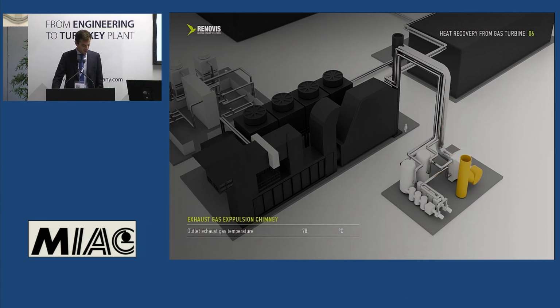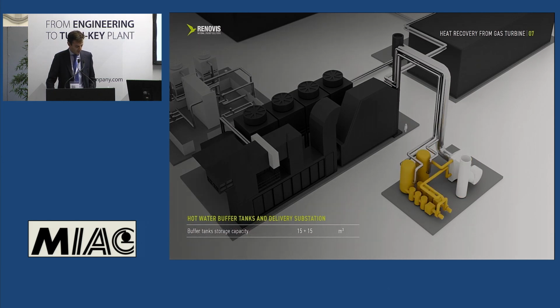Recovering thermal energy from the fumes obviously means that they undergo a cooling down to about 78 Celsius degrees, and they are then expelled into the atmosphere by means of a new chimney, specifically built for this purpose. The hot water generated through the heat recovery is stored in two inertial tanks of 15 cubic meters each. Their function is to temporarily separate the production of hot water by means of thermal recovery from its use, optimizing the efficiency of the overall system.